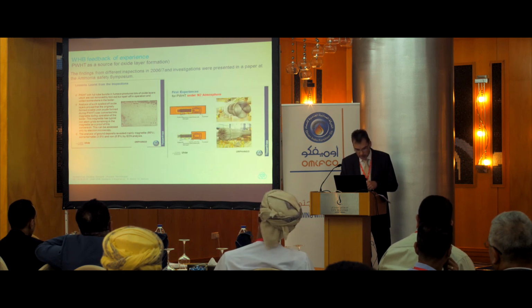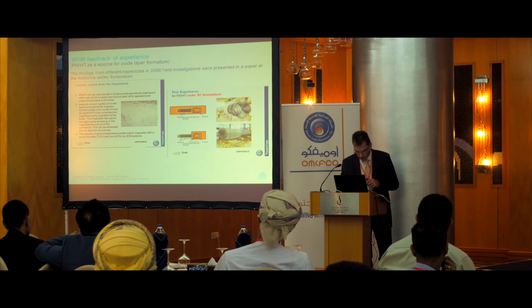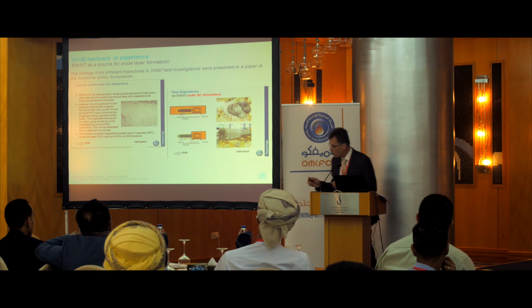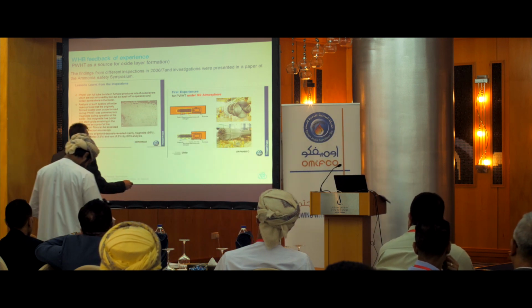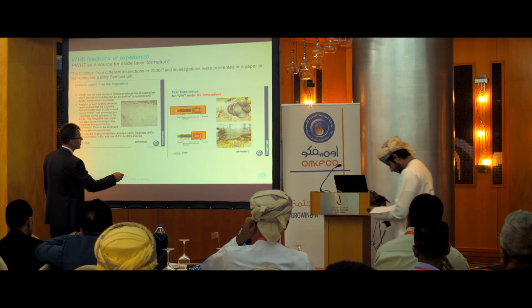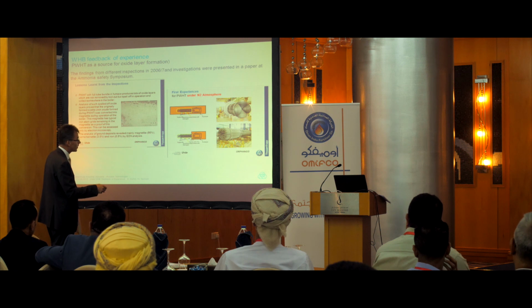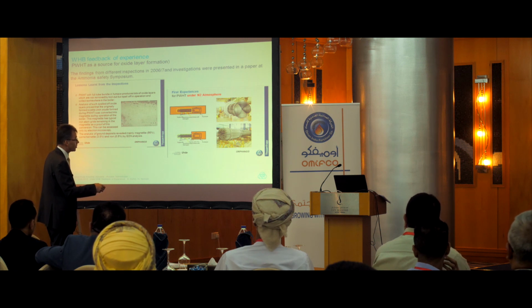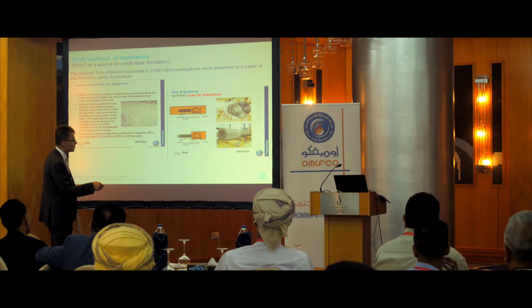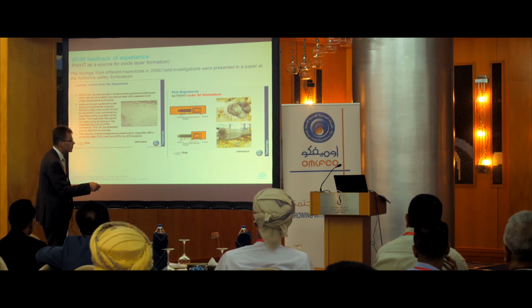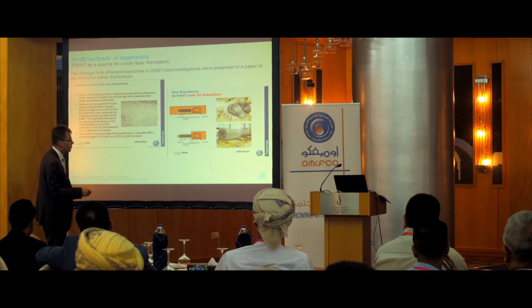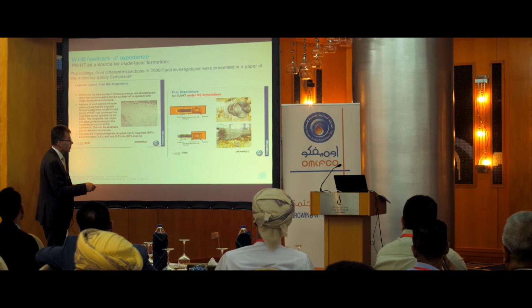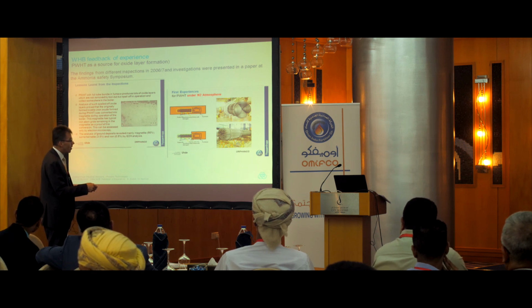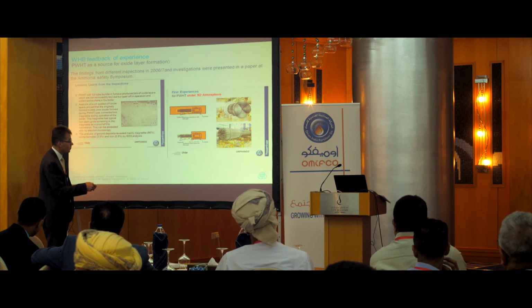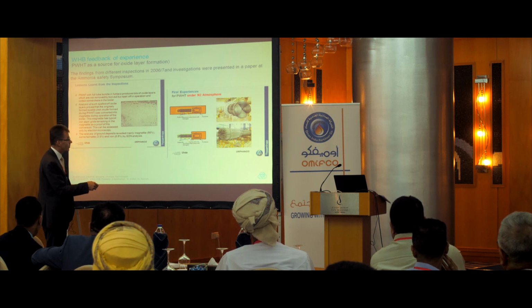Thus, all post-weld heat treatment of Uhde waste heat boilers were done since 2007 with an auxiliary shell. This is shown on the right side. I hope you can see the yellow. If you have a configuration where you do not have a big furnace, some of the manufacturers have only small furnaces. So interesting for heat treatment is this part, tube sheet shell connection, for example. This is inside the furnace. Outside the furnace was always the tube bundle. In former times, there was no auxiliary shell, we call it, around this tube bundle and also welded here temporarily to the shell, to the tube sheet. This was done, and we have been able to feed in now nitrogen to blanket the whole tube bundle and to avoid any oxidation, any build up of oxide layers.